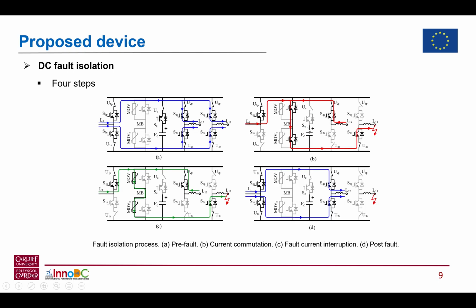For the DC fault isolation of the proposed device, there are normally four steps in order to isolate a DC fault. The first one is the normal operating condition. The current can flow through both the positive and the negative branches. When a fault is detected, the mechanical switch and the power electronic switch will be switched off in order to redirect the fault current into the main breaker. After that, the main breaker can be switched off to isolate the DC fault.